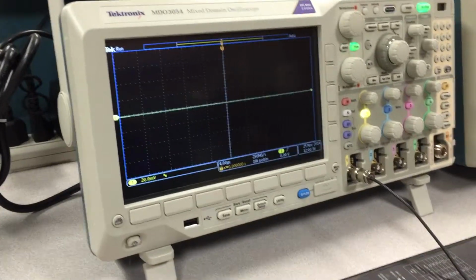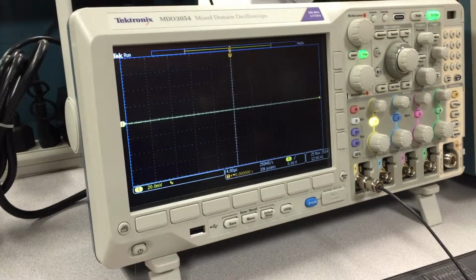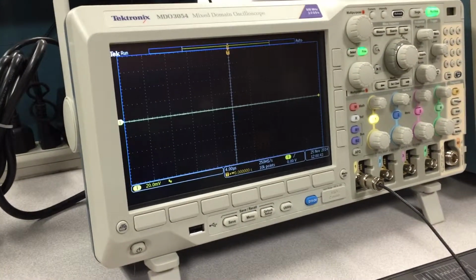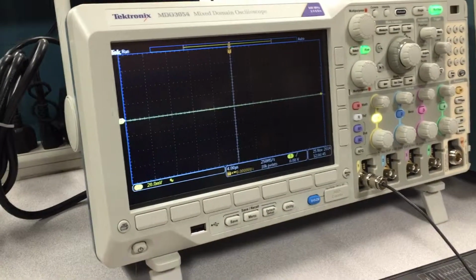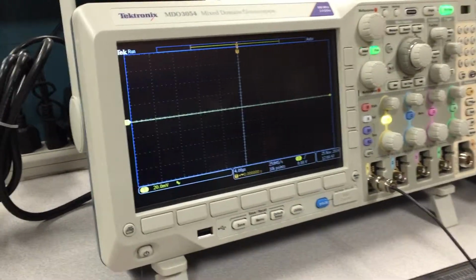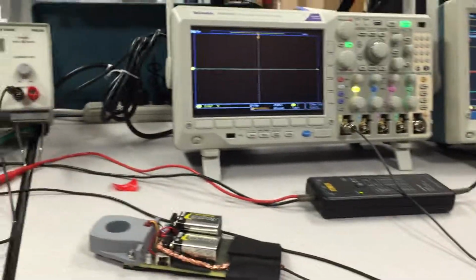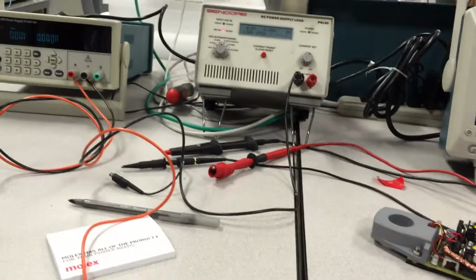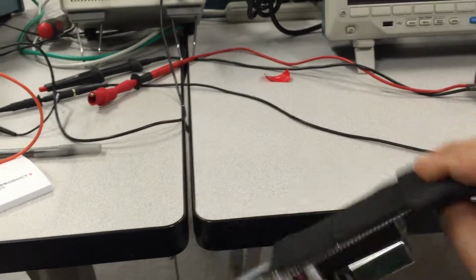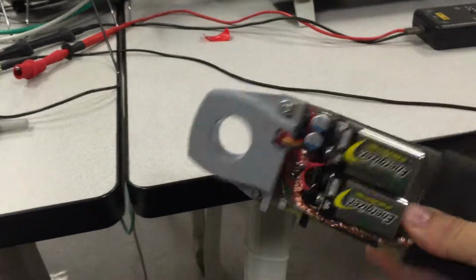Since we were asked to make some relatively accurate power measurements, we're going to need to calibrate some of our probes and make sure that we are taking care of calibration and deskew so we can measure switching losses relatively accurately. Since we don't have any fancy tech VPI stuff here, we're working with some fairly crude probes, but they will do the job. This is basically a homemade high-frequency current probe that we use here.